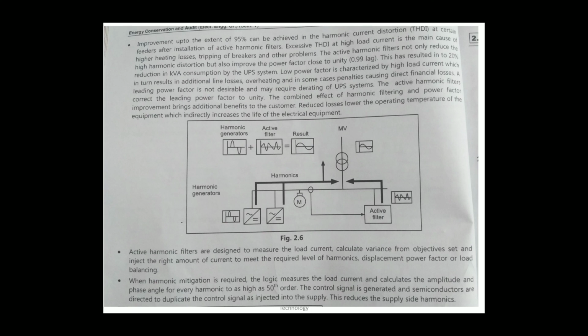Active harmonic filters are designed to measure the load current, calculate the variance from objectives set, and inject the right amount of current to meet the required level of harmonics, displacement power factor or load balancing. When harmonic mitigation is required, the logic measures the load current and calculates the amplitude and phase angle for every harmonic up to as high as the 50th order. The control signal is generated and semiconductors are directed to duplicate the control signal as injected into the supply. This reduces the supply side harmonics. The diagram shows the block diagram of the active harmonic filter.